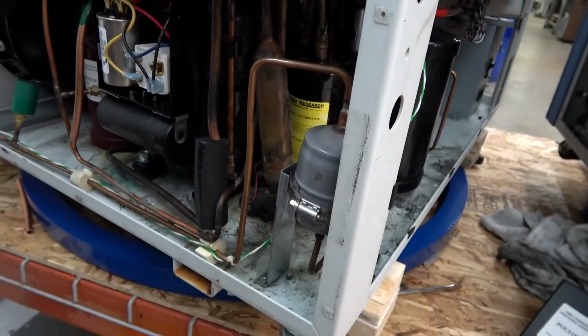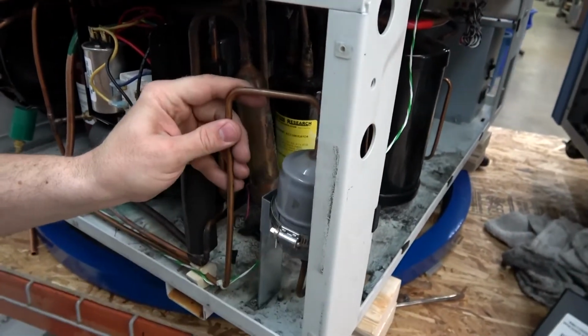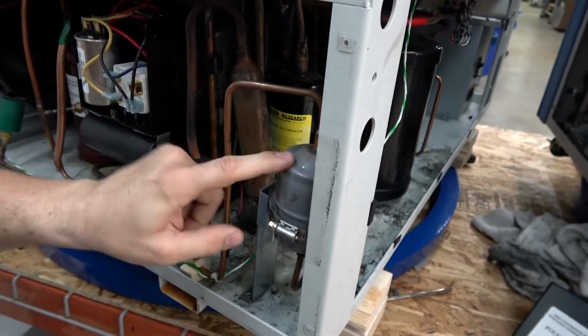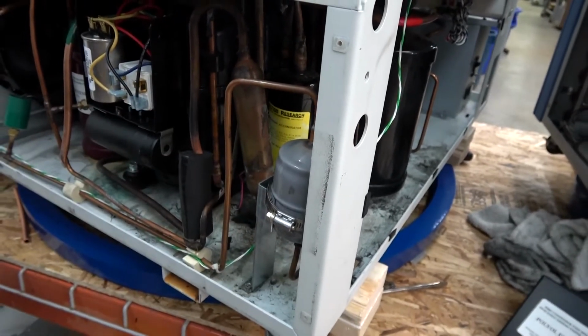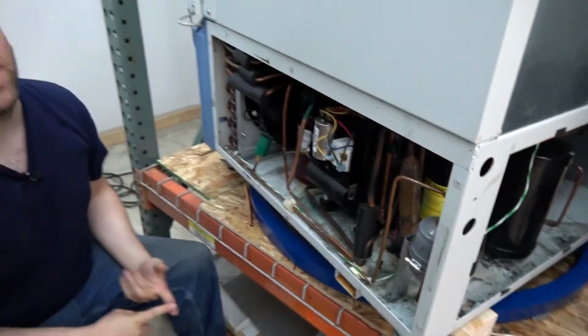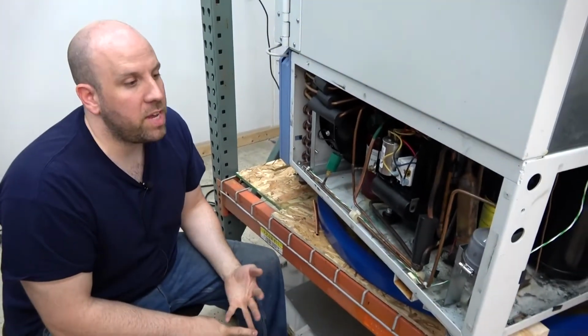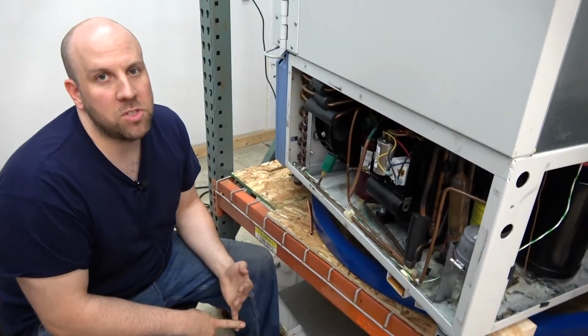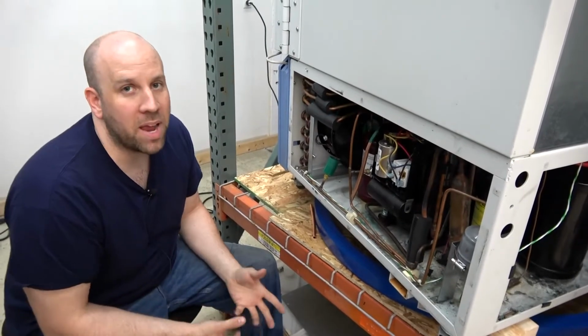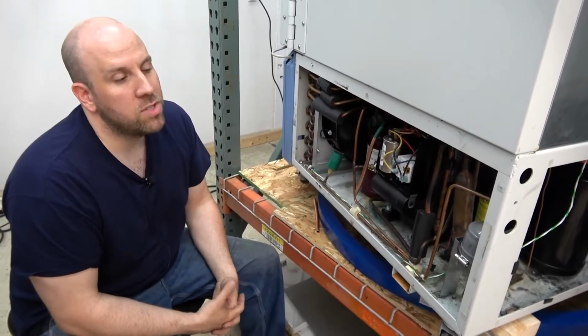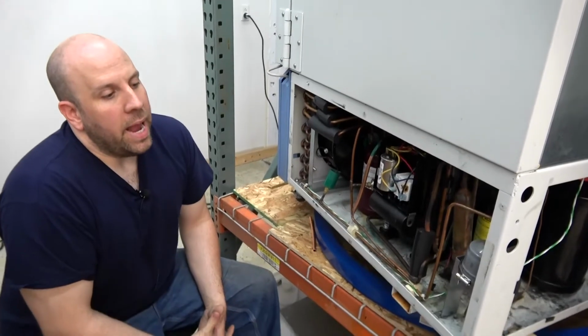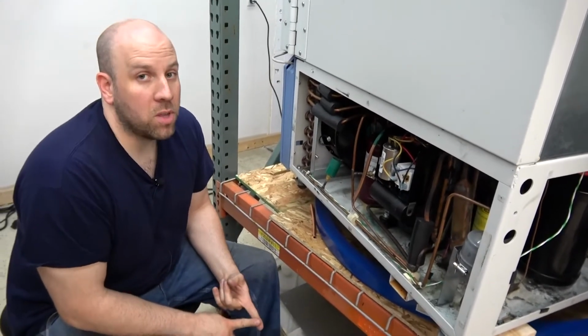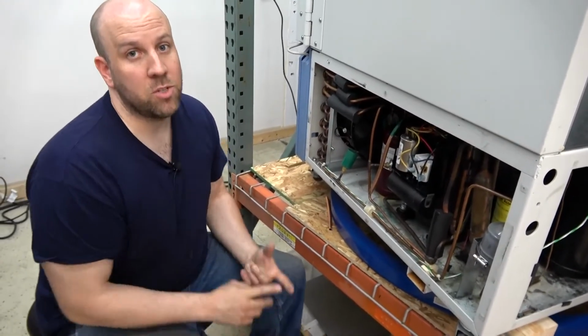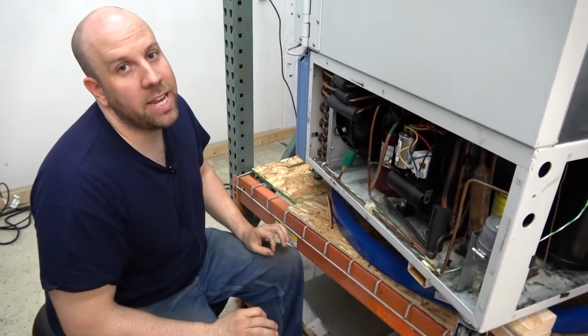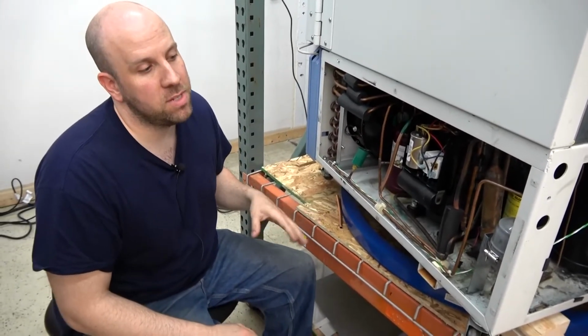This is a liquid line filter dryer, so the refrigerant should be in a mainly liquid state when it comes through here. It filters out small particles like metal shavings, very, very small dirt and other debris that might get its way in there at some point while servicing or manufacturing. And very importantly, it removes moisture from the system. It traps water in there, and it can remove acid from the system.